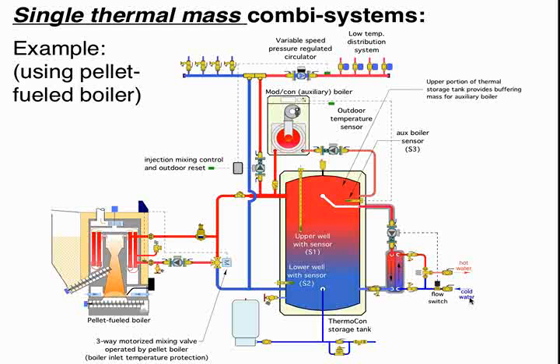So we're going to use the upper portion of the thermocon tank for the buffering. What we have over on the right is an on-demand domestic water heating assembly, and it's a pretty simple idea. We have a heat exchanger. This would typically be a stainless steel brazed plate heat exchanger. We have a flow switch. When somebody opens a tap for hot water, the flow switch contacts close. Through a relay, we turn on this circulator. We bring hot water, and this white line just represents the thermocon tank.